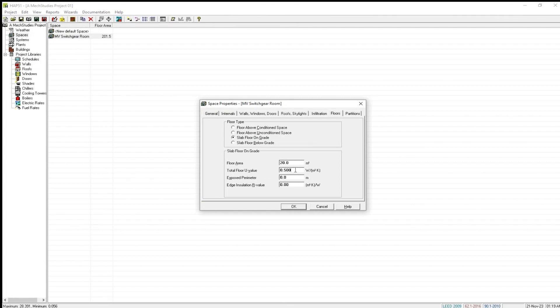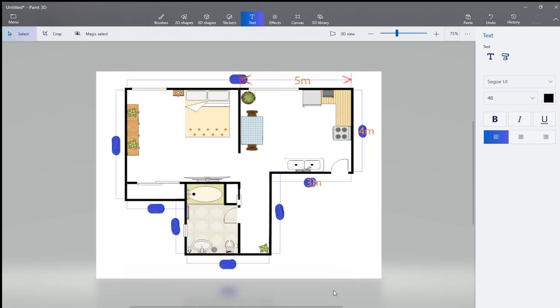The total floor U-value here is 0.5, which is acceptable. If there is insulation below the floor, we have to consider that insulation as well, and accordingly the floor U-value has to be considered. For our example, we are considering 0.5. The exposed perimeter means the chances of heat ingression through the exposed perimeter.